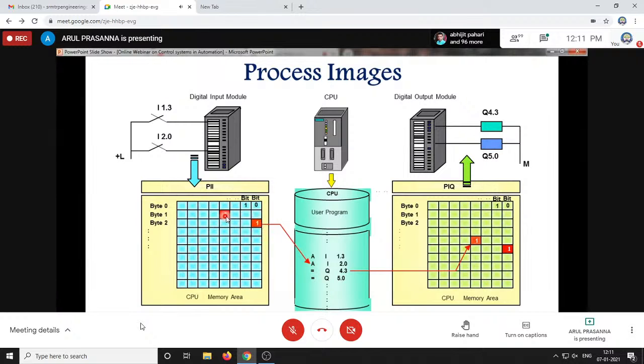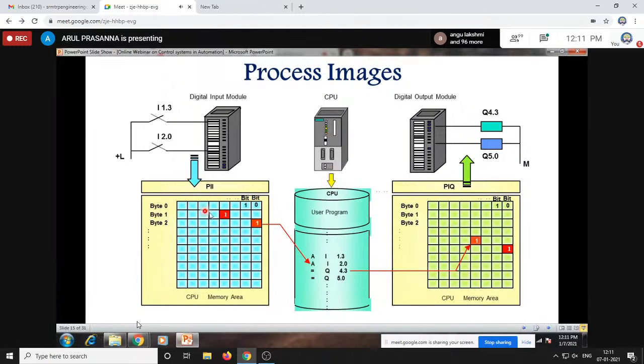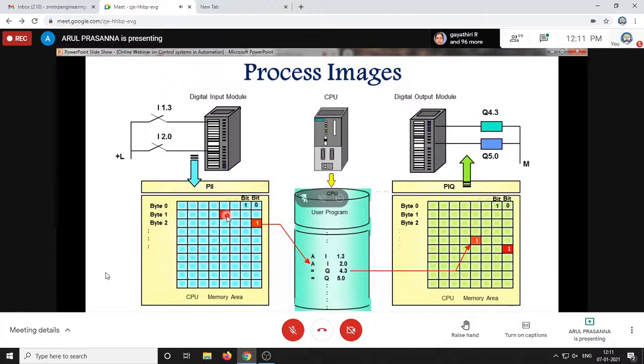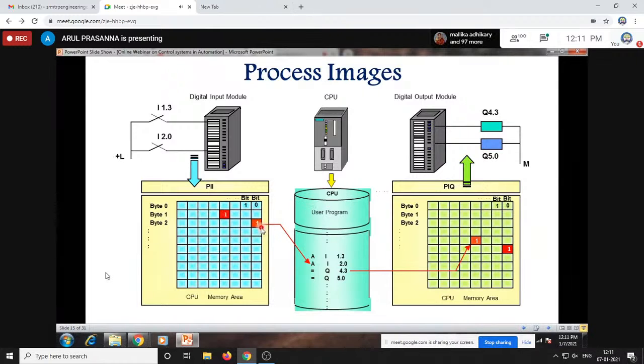So now these two updated values are scanned by your CPU. The CPU will come into the PII chart and scan this chart, and here we have two updated values changed from 0 to 1. So now it will go for the user program. With the user program, it will check for any updation in your output that is meant by the programmer. Then it will update in the PIQ chart. See here, there we have an update: if A, that is I 1.3, is turned on, then Q 4.3 is to be turned on. So this is what the program that is done inside your PLC.